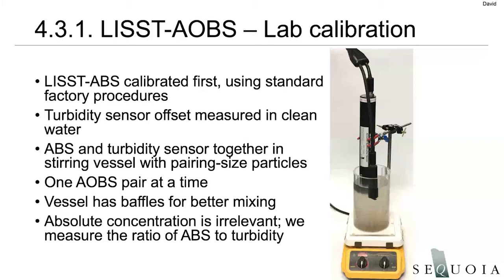The AOBS calibration is something that happens after the ABS has been completely calibrated through the process I described earlier. And then we put in a turbidity sensor and the ABS together with these 30 micron particles. We're using Arizona test dust that's sieved in the 20 to 40, I believe, 20 to 40 micron range. So its median is 30. We do this because it's not a very long, complicated process. We usually do this one pair at a time in this smaller tank.